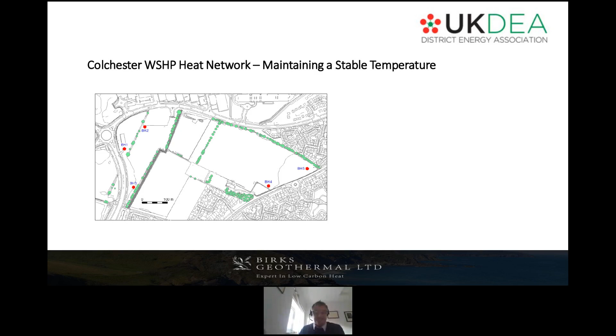And also at Colchester Gateway, this is looking at the hydraulic parameters. What we're looking at here is a period of 1 week where we were abstracting from 2 abstraction wells, each at 9 litres a second, so about 35 tonnes an hour from each. This resulted in a drop in water levels in the abstraction wells of around 40 meters, and a rise in the reinjection boreholes of about 60 meters, starting to stabilize towards the end of the interval.